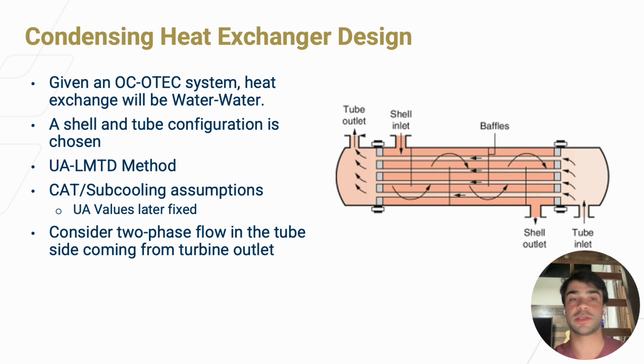Now moving on to the condensing heat exchanger design. Since we have an open cycle OTEC system, the heat exchange will be from water to water, and so a shell and tube configuration is chosen. Here we're going to be using the UA-LMTD method, where we're going to be initially assuming our close approach temperatures and subcooling temperatures, and later fixing our UA values to design the heat exchanger.